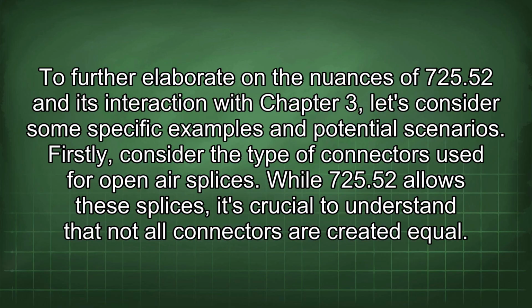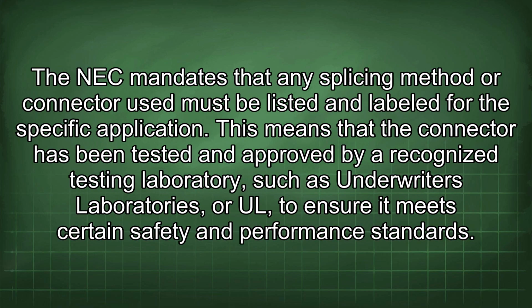Firstly, consider the type of connectors used for open-air splices. While 725.52 allows these splices, it's crucial to understand that not all connectors are created equal. The NEC mandates that any splicing method or connector used must be listed and labeled for the specific application. This means that the connector has been tested and approved by a recognized testing laboratory such as Underwriters Laboratories or UL, to ensure it meets certain safety and performance standards.